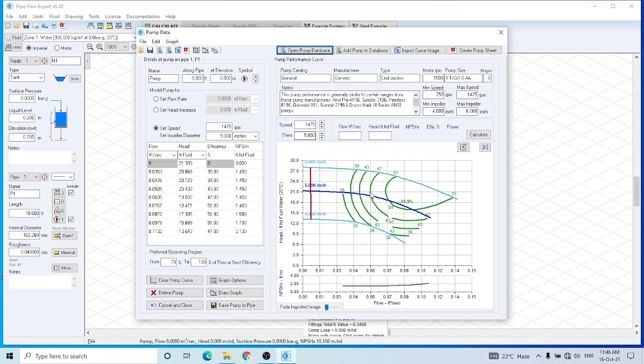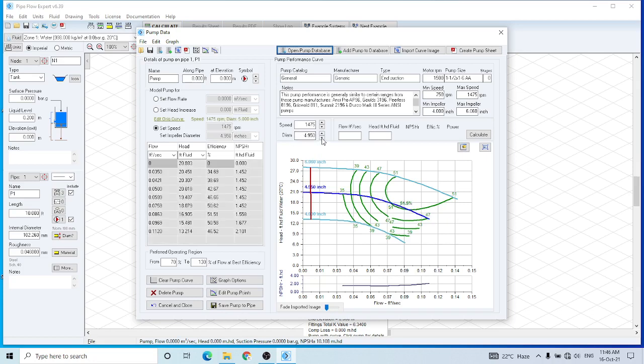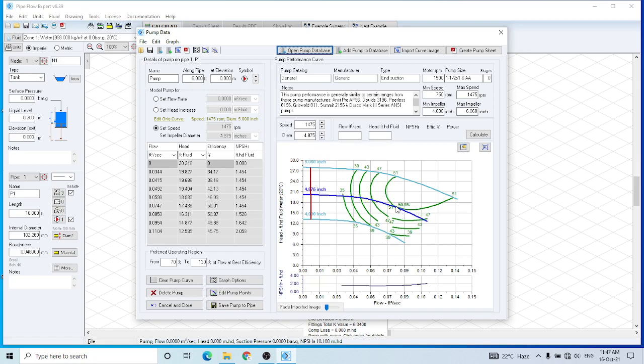The 5-inch curve is just here, this blue one. I want to move it slightly below, so I would decrease the diameter of the impeller. And you can see that it is moving downwards. And here is the best efficiency point.